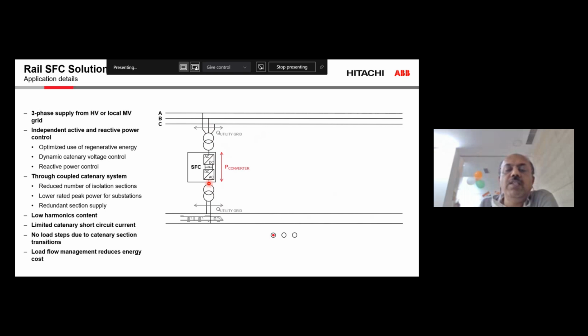So overall efficiency of the railway network will increase. It will reduce the real power demand to the extent of 20% or more, and not only that, it will improve the overall efficiency of the network by compensating the reactive power and reduction of the losses. Plus it will also take care of the grid code requirements like harmonics and reactive power mitigation at the network level.